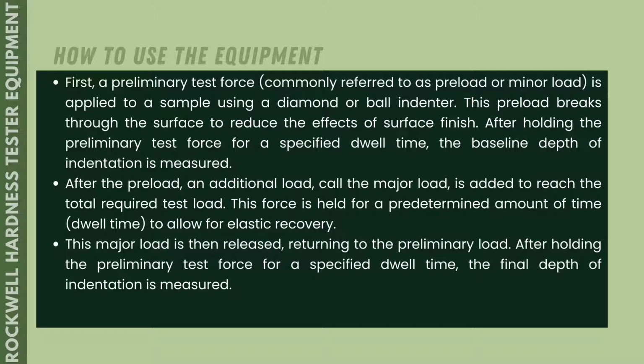After the preload, an additional load called the major load is added to reach the total required test load. This force is held for a predetermined amount of time, the dwell time, to allow for elastic recovery. This major load is then released, returning to the preliminary load. After holding the preliminary test force for a specified dwell time, the final depth of indentation is measured.